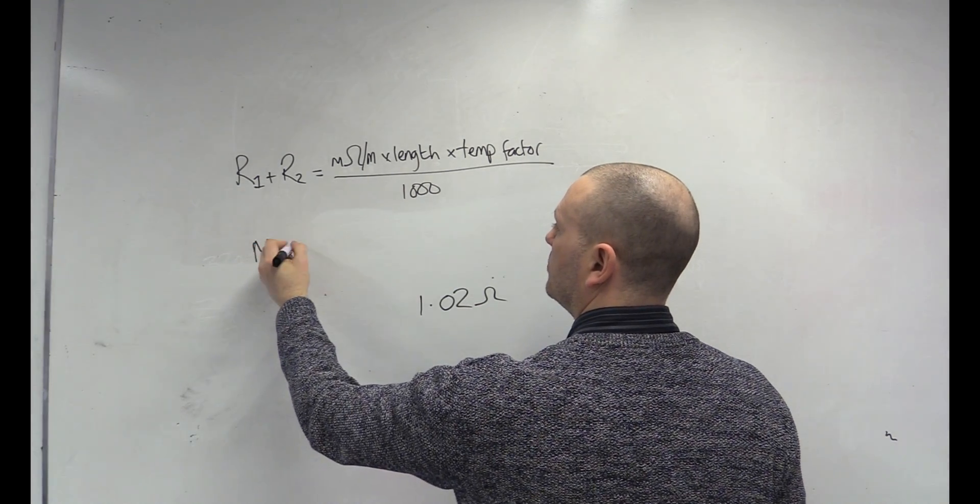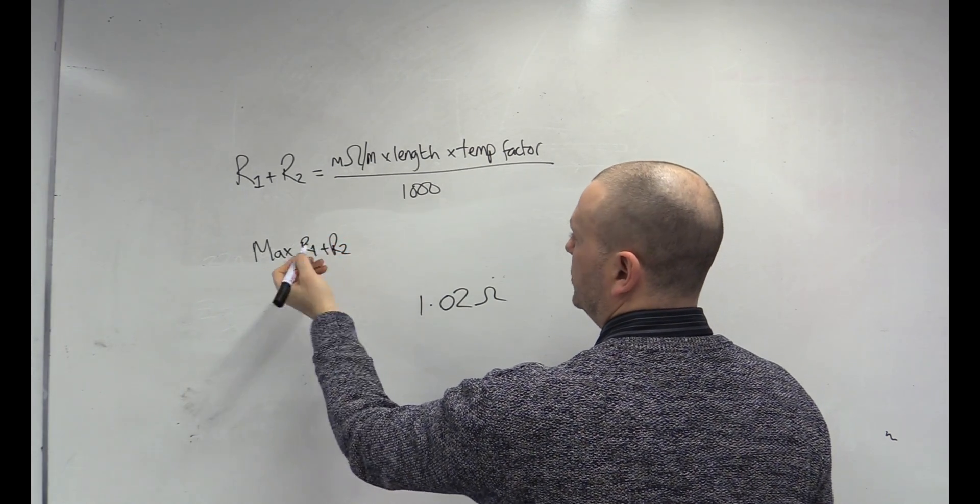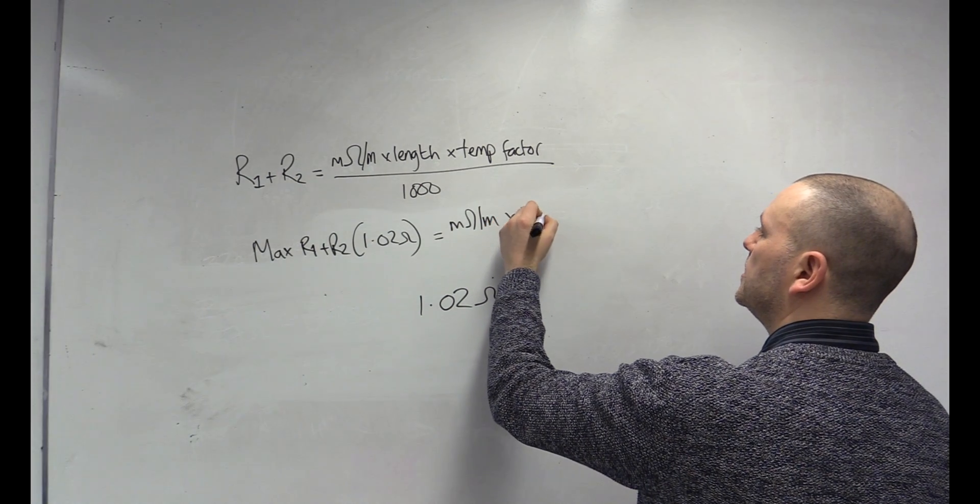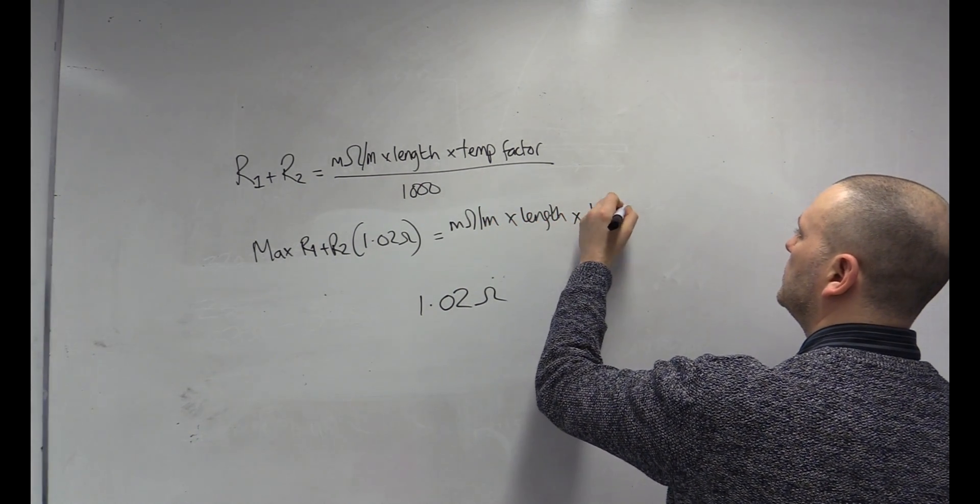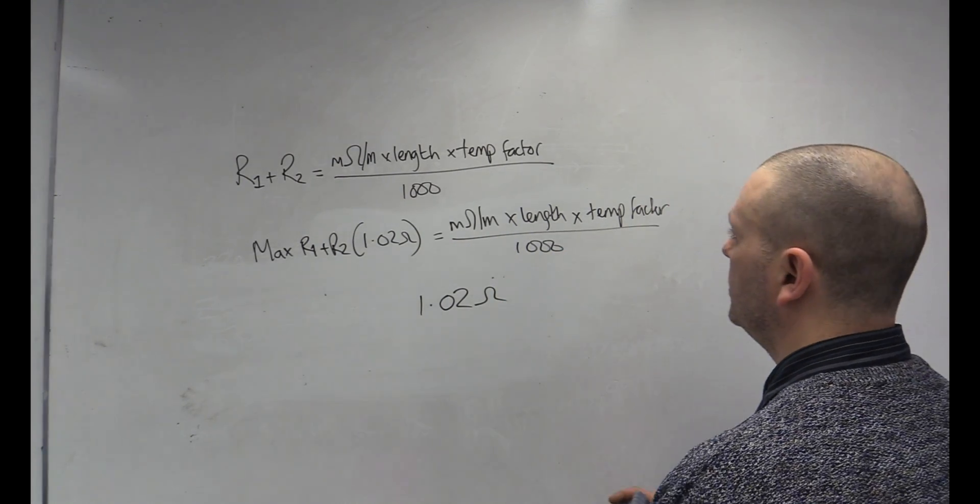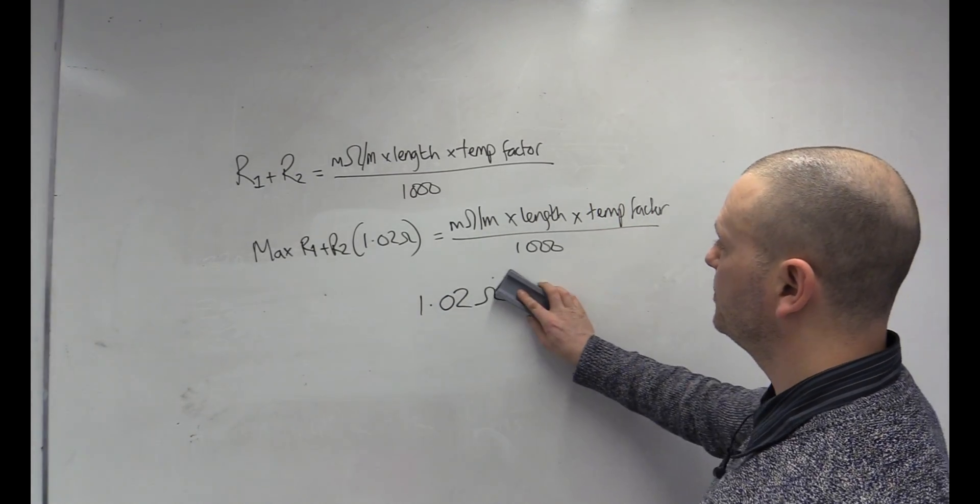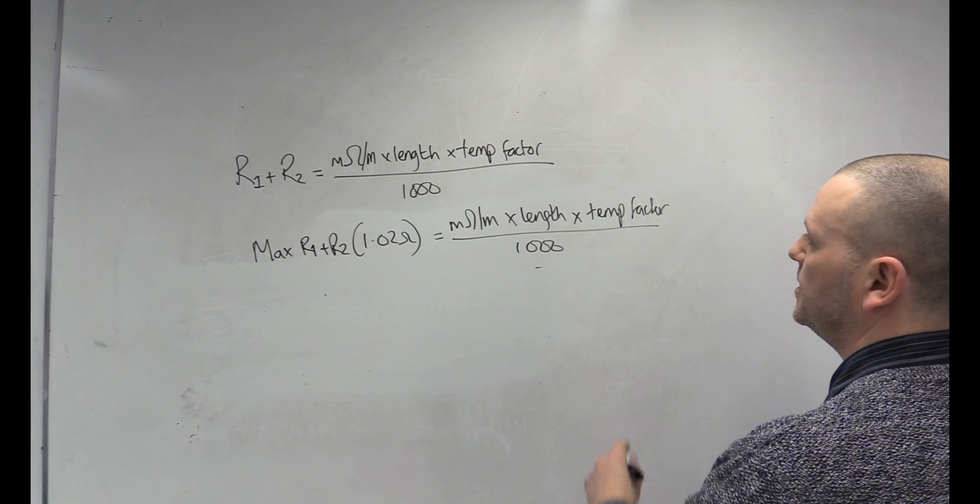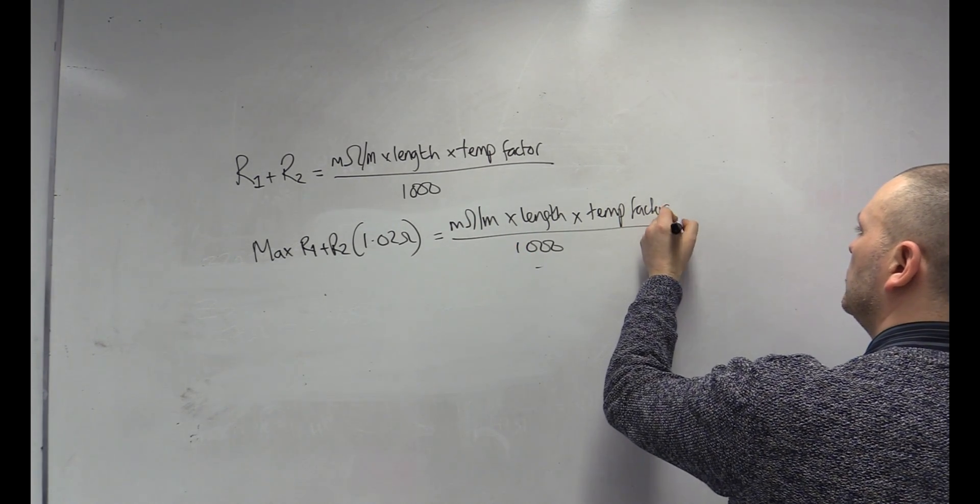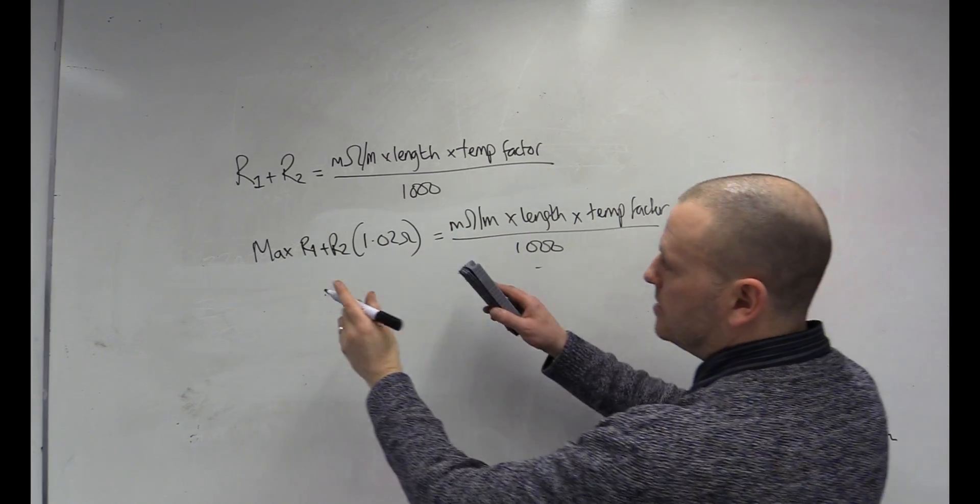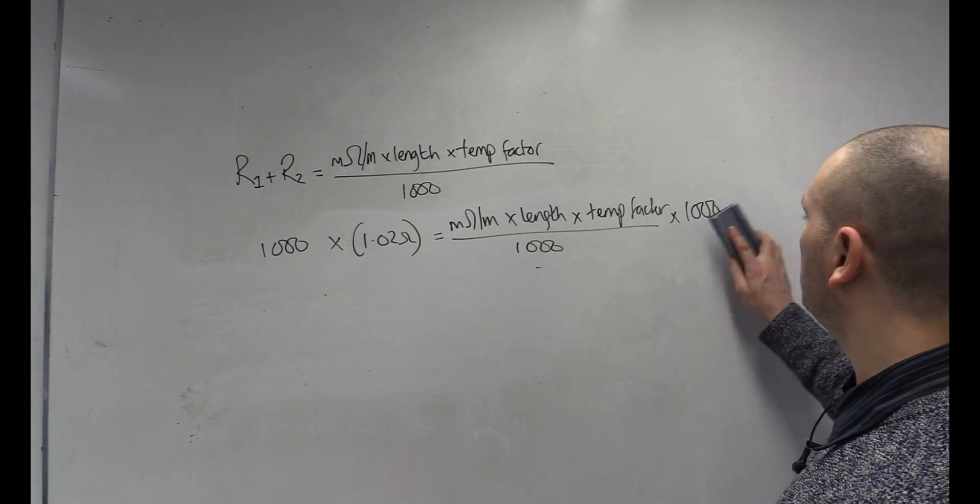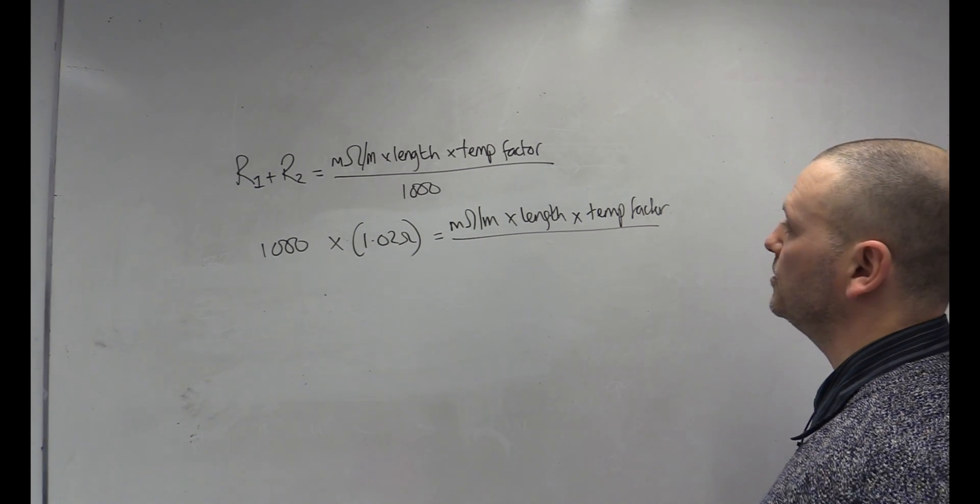So, let's put that in instead of R1, R2. So, max R1, R2, which is 1.02 now, is equal to milliohm per meter times length times the temp factor divided by 1,000. So, now we just need to transpose this equation and make sure that we've got everything in the right place. So, transposition says, get anything downstairs, upstairs first. We've got to cancel out the 1,000, so we're going to do the opposite function by itself. At the moment it's being divided. So, I'm going to multiply it by itself. I've unbalanced it. I need to copy it. Let's get rid of that. Times 1,000. And then we could leave it there. It is balanced, but there's no sense in doing it. 1,000 divided by 1,000 is 1. It's not doing anything. Get rid of it.